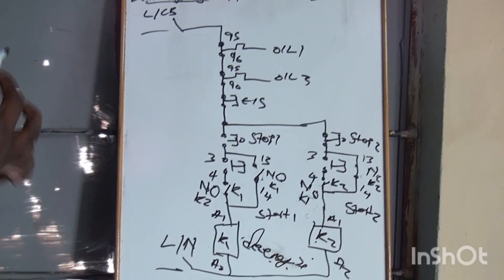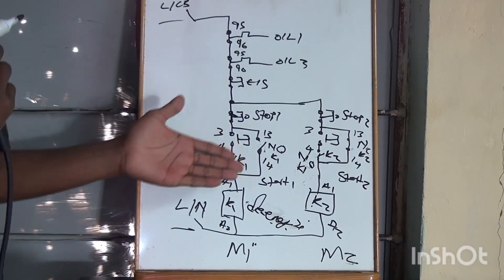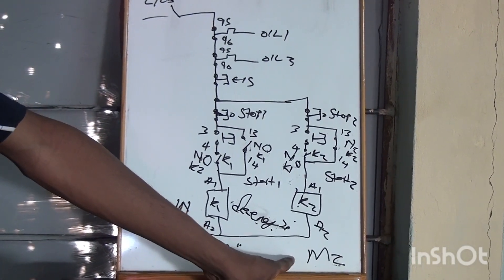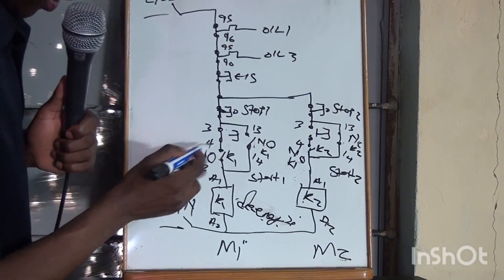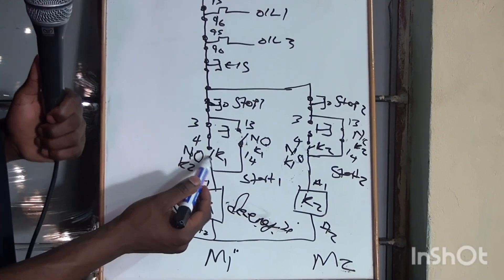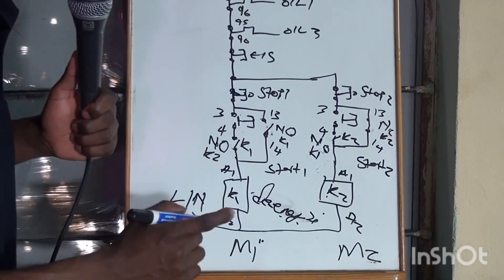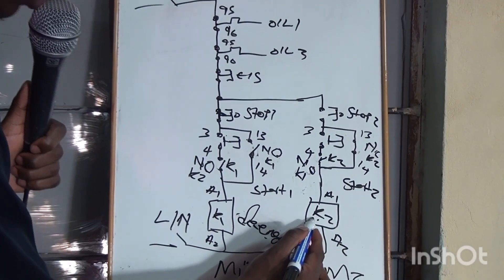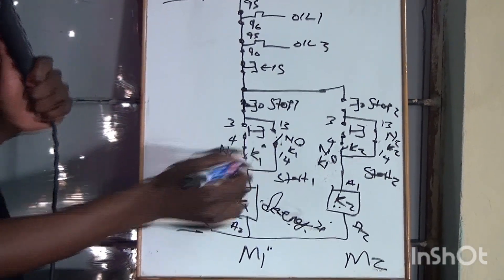You've stopped Motor 1. When the coil de-energizes, the normally closed contact becomes normally open again. You try to press the start button to restart Motor 1, but current tries to run and finds a normally open contact from K2 — so it can't get through. Motor 1 cannot be restarted while Motor 2 is running. However, if you decide to stop Motor 2, the K2 coil de-energizes, that contact becomes normally closed again, and now you can restart Motor 1.